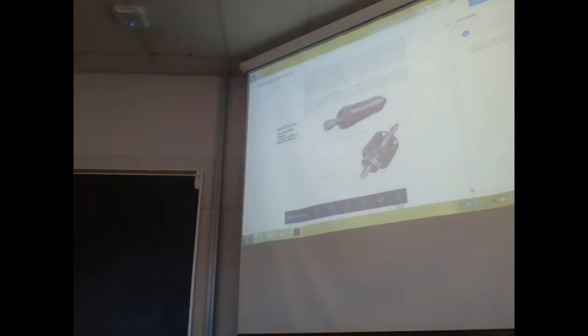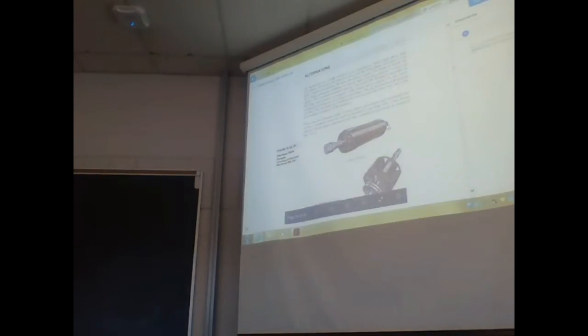AC generators are usually referred to as alternators. Both single-phase and three-phase alternators are manufactured, but the three-phase alternator is far more common in industry. Modern alternators consist of a stator on which the AC voltage-producing windings are placed, and a rotating armature or rotor on which a DC excitation winding is placed.